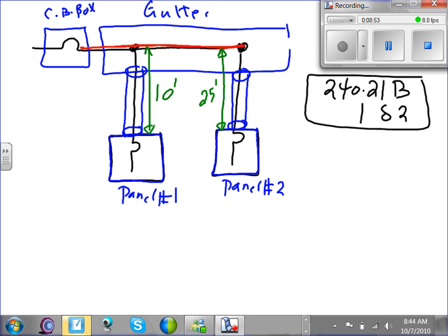And tap rule number 3 is different for both of them. Tap number 3 for the 10-foot tap, guys, it says the overcurrent protection device for the feeder cannot be more than 10 times the conductor ampacity. And for the 25-foot tap, the conductor ampacity cannot be less than 1/3 of the overcurrent device.